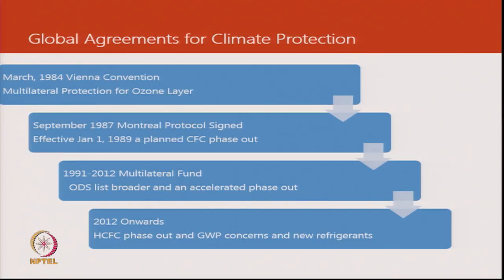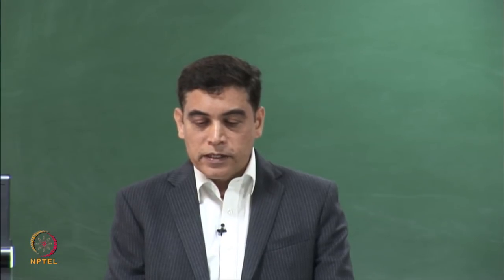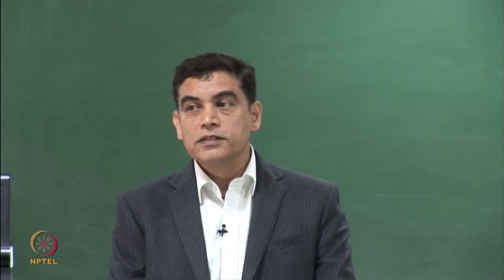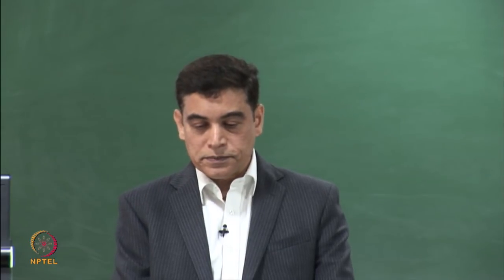In this slide, what I want to communicate is that refrigerants like CFC-11, introduced in 1932 as a replacement for flammable and toxic refrigerants used at that time, became very popular and was used widely in centrifugal chillers. Today it is classified as an A1 refrigerant - we'll talk about safety classification for refrigerants later. It has an ODP, ozone depleting potential, with a reference number of 1, meaning it is among the highest ozone depleting substances.